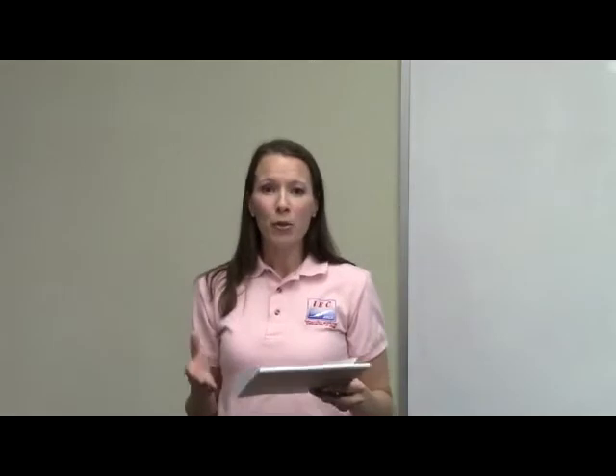Let's talk about buck boost for a minute. A buck boost transformer, what is it? Well, it's an auto transformer, which is an electrical transformer with only one winding. All right, let that sink in for a minute. A transformer with only one winding. Portions of the same winding act as your primary and your secondary, and we'll get into that in just a second with a diagram. The winding has at least 3 taps where connections are made.